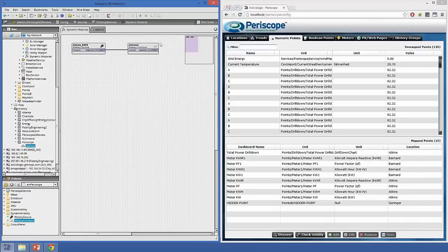So that's pretty cool, but what if we wanted to add a couple histories together? So we had 2 submeters and we wanted to get the total, but the systems integrator did not perform that calculation. So again, you could go into AX and do that logic, but it would just start now. So the benefit of doing it through dynamic histories is that it goes all the way back in time to the beginning of the history and keeps up to the future as well.